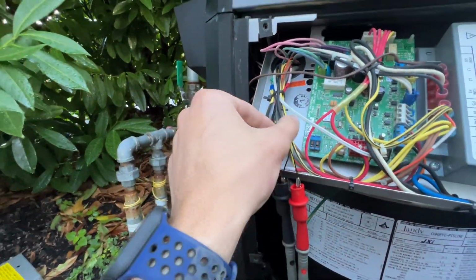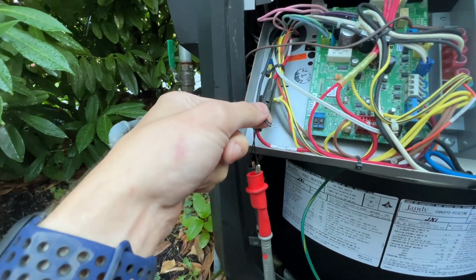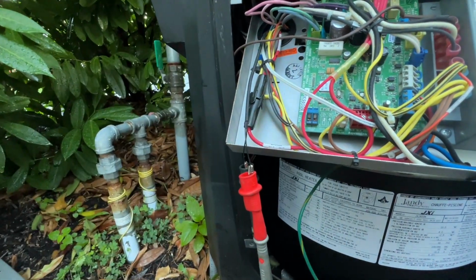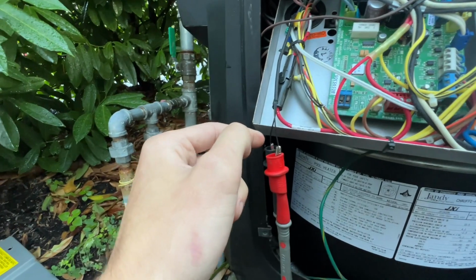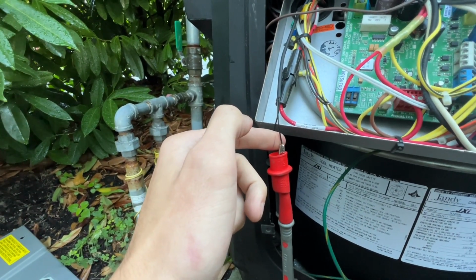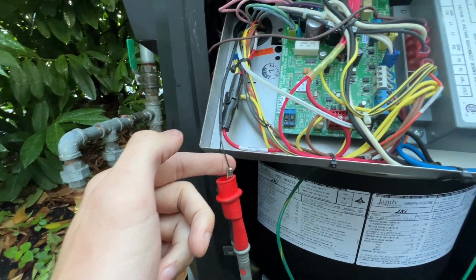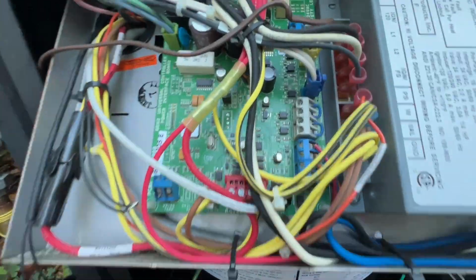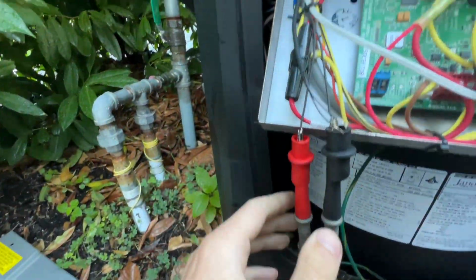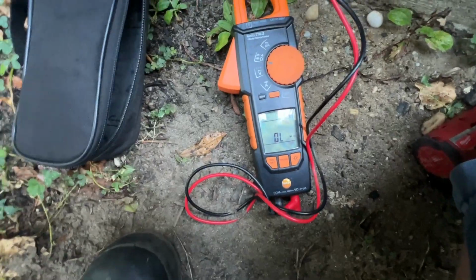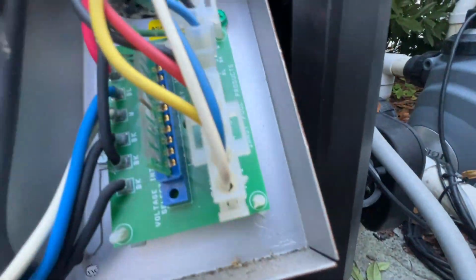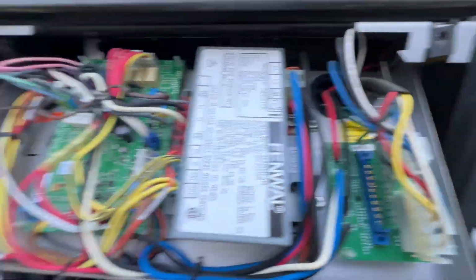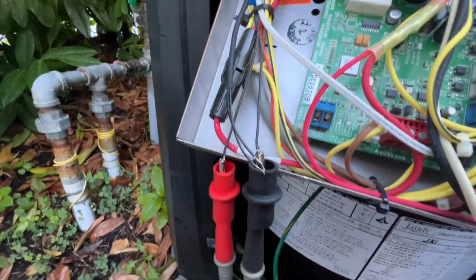Just for fun, I'm going to test the other sensor as well, just to see what that one's reading. With a good temperature sensor, that means it's going to be the control, which is this right here. With my leads on the other sensor, I'm getting OL. So my feeling is that the sensor wires were cut when the sensor was replaced — it's not just sitting in there.